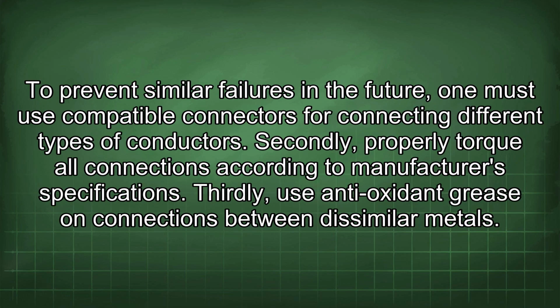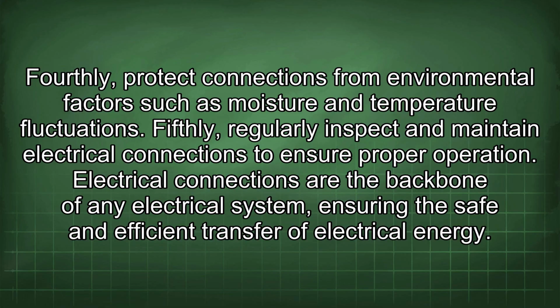To prevent similar failures in the future, one must use compatible connectors for connecting different types of conductors. Secondly, properly torque all connections according to manufacturer's specifications. Thirdly, use antioxidant grease on connections between dissimilar metals. Fourthly, protect connections from environmental factors such as moisture and temperature fluctuations. Fifthly, regularly inspect and maintain electrical connections to ensure proper operation.